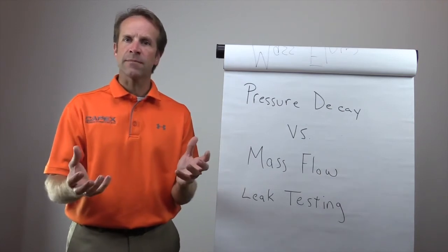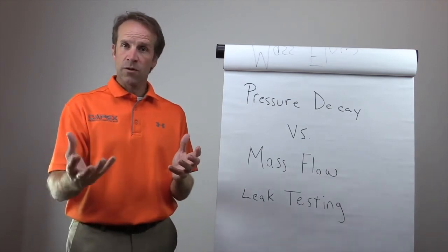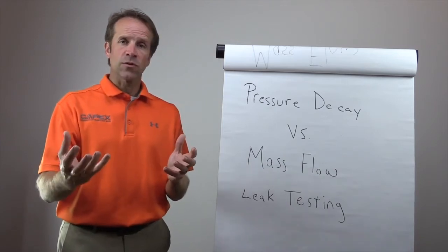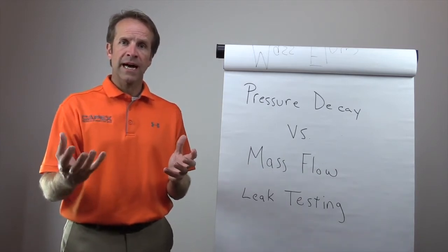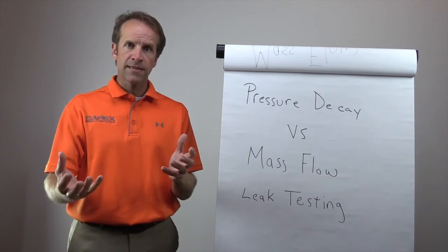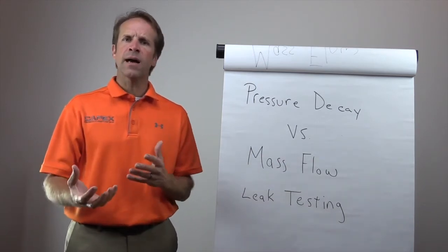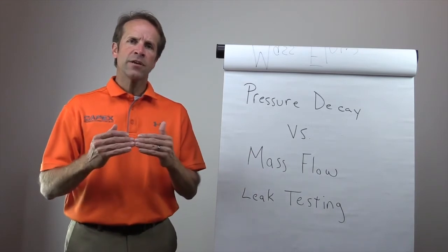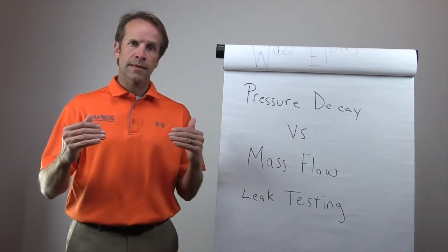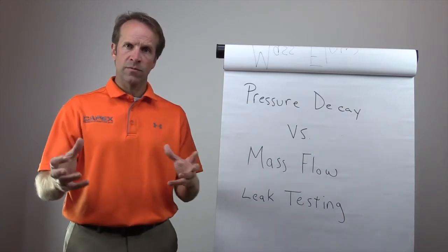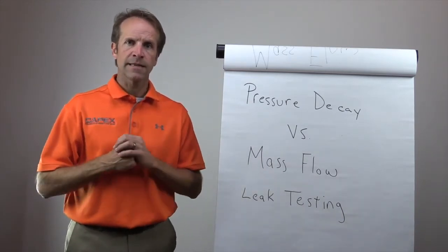They're not the same. And so therefore, the smaller volume pressure loss will be a higher leak rate than the basketball. So we have to keep in mind that we can't have a universal standard if we are testing multiple volume parts with pressure decay leak testing.